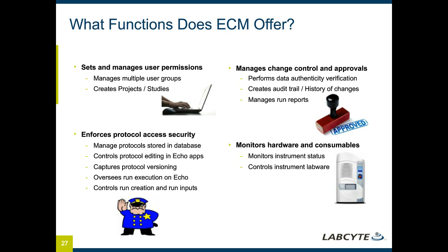That old version, though, persists within the system. And then it oversees the runs that are being transferred to the Echo. So only those folks who have access to that functionality will be able to run particular protocols on the Echo. And then it controls the run inputs and the run creation. It also manages the change control and approvals side of things. So anytime a change is made to a protocol, it requires approval, and there is an audit trail for that.